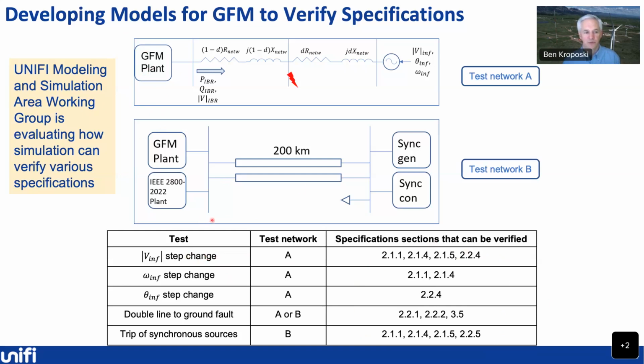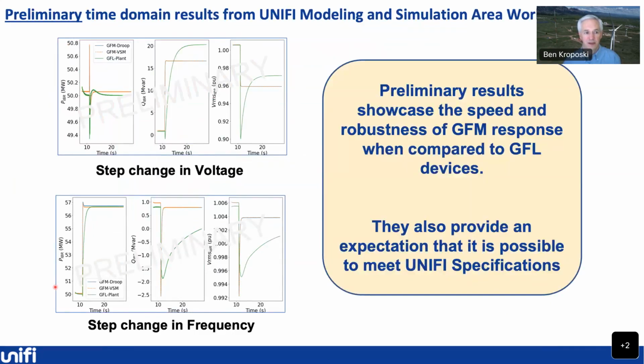So we're working our way through a variety of test network use cases to verify that as these specifications get developed, there's a set of modeling and simulation technologies and programs available to verify that output. Some quick little preliminary results, right? We wanted to do a step change in voltage, and then we're looking at various types of grid forming technologies, whether it's droop or whether it's virtual synchronous machine or whether you have a grid following plant, and evaluate what the response characteristics look like to step changes in voltage and step changes in frequency. Again, with the idea that we'd be able to validate some of those specifications in just the modeling and simulation area.